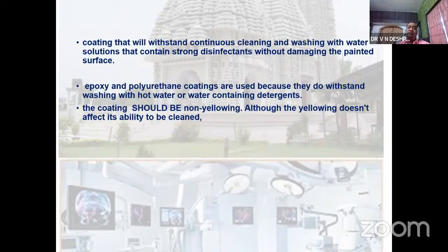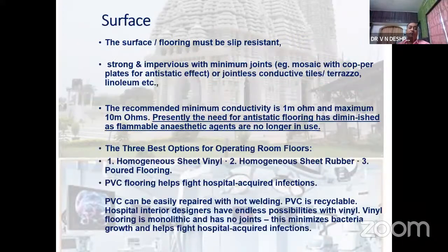Coating of the wall should withstand continuous cleaning, washing with detergents and disinfectants, and it should not damage the paint. Epoxy and polyurethane coats are used because they withstand washing with hot water, detergents, and disinfectants. The coating should be non-yellowing, so that it does not hamper cleanliness or cause germ or fungus generation in the operation theater. But whatever color we choose, it should be maintained for a longer period.